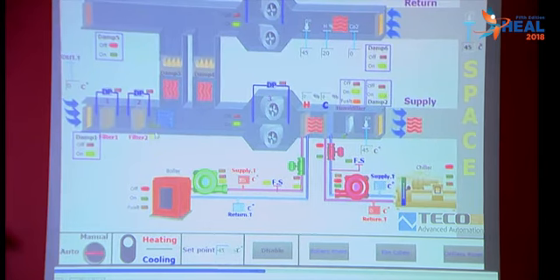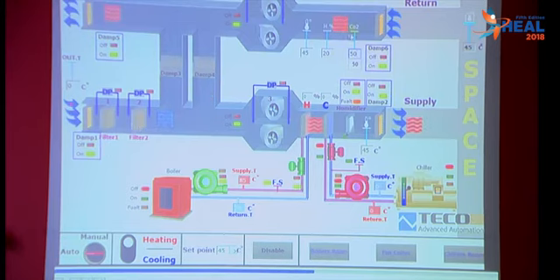Let's discuss some cases. For CO2 level, if we have a high CO2 level, let's say 50, we see that damper number 3 and damper number 4 are closed. So only the fresh air will come to the space, and the CO2 will go out from this damper, the exhaust damper. Okay, let's see another case. If we have humidity that reaches lower than 40%, as we see here, the humidifier is working. If it's higher, let's say 50, it will turn off and the air is ready to come to the space.